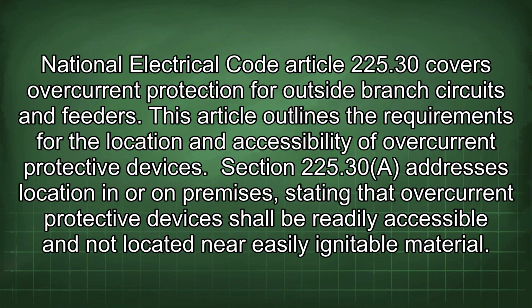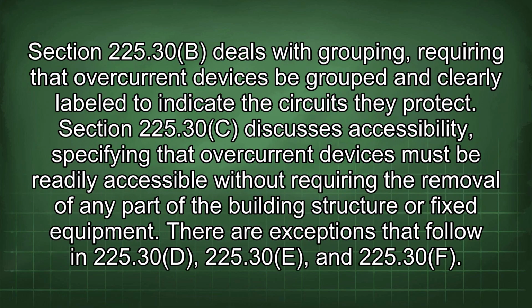feet away. National Electrical Code Article 225.30 covers overcurrent protection for outside branch circuits and feeders. This article outlines the requirements for the location and accessibility of overcurrent protective devices. Section 225.30a addresses location in or on premises, stating that overcurrent protective devices shall be readily accessible and not located near easily ignitable material. Section 225.30b deals with grouping, requiring that overcurrent devices be grouped and clearly labeled to indicate the circuits they protect.